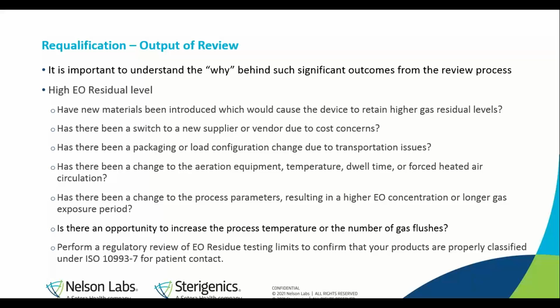The next output of the review may be a high residual level. And some of the questions that need to be investigated or asked about this follow. Have new materials been introduced which would cause the device to retain a higher gas residual level? Has there been a switch to a new supplier or vendor due to cost concerns? Has there been a packaging or load configuration change due to transportation issues? This would be to and from the contract sterilizer, at the sterilizer itself, and then transportation to perhaps the distribution warehouse or the end of where the product needs to go.